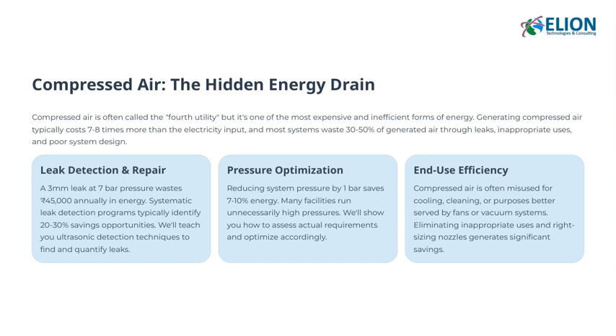Finally, we need to look at end-use efficiency. Often, compressed air is misused for cooling, cleaning, or other purposes that could be better served with fans or vacuum systems. By eliminating these inappropriate uses and properly right-sizing nozzles, we can achieve significant savings. All these strategies, detecting leaks, optimizing pressure, and improving end-use efficiency, are critical parts of reducing the hidden energy drain caused by compressed air. They help us cut costs, improve efficiency, and align with our overall goal of sustainable and cost-effective operations.